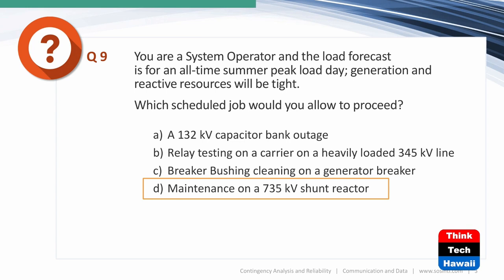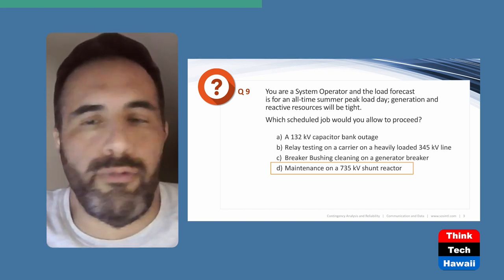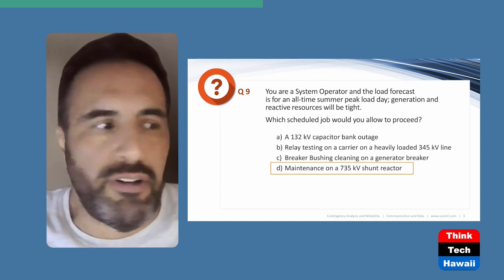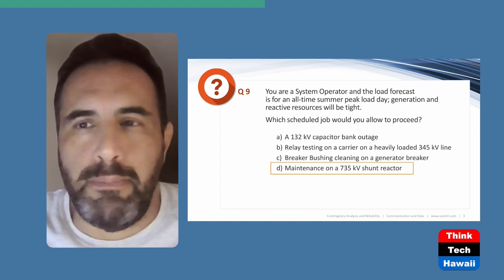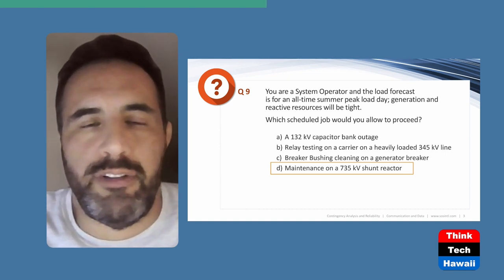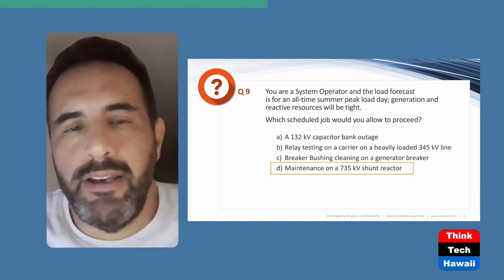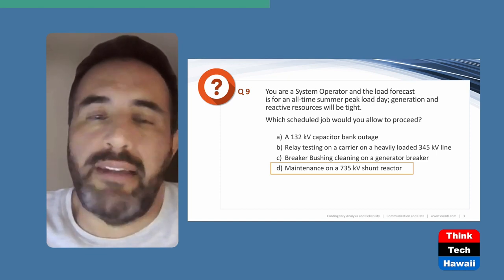Capacitors are normally switched out at night when there's excess voltage — you don't need voltage support during the day, so A is not the answer. Relay testing on a heavily loaded 345 kV line is the last thing you want to do — accidents happen, somebody could bump a cabinet, pick up a relay, and accidentally trip something. Keep your hands in your pockets — no testing at this time. B is not a good answer.